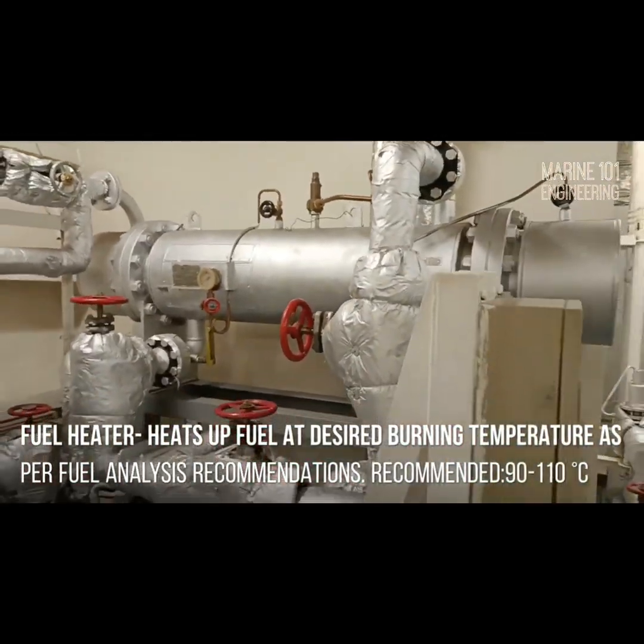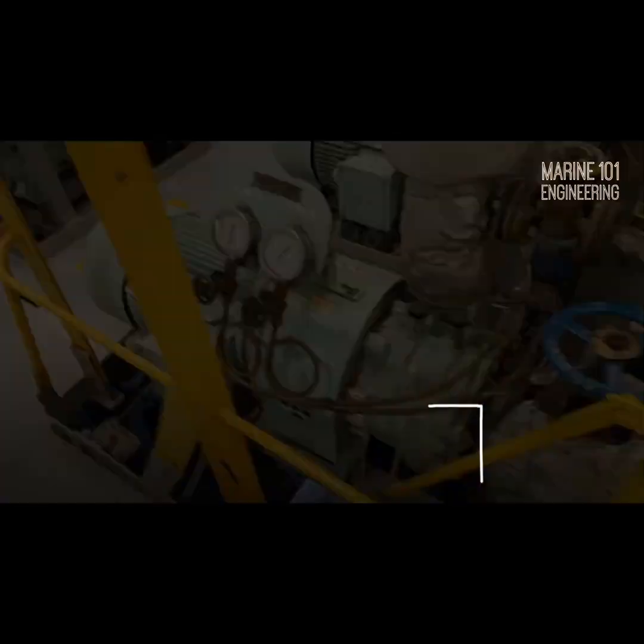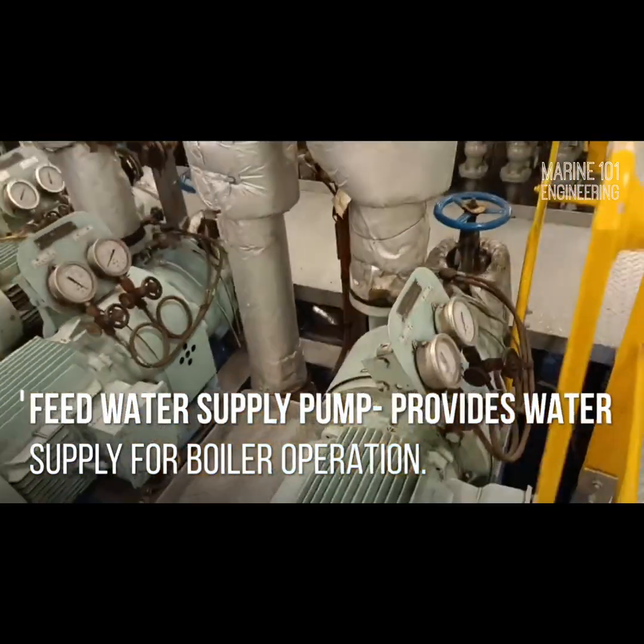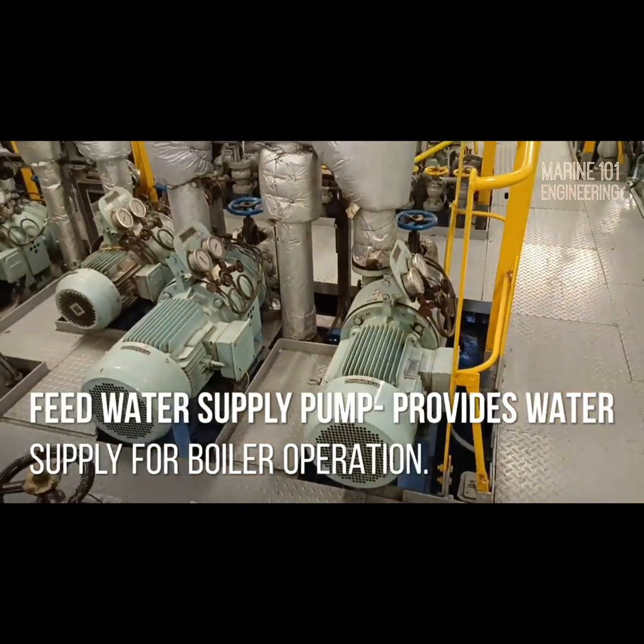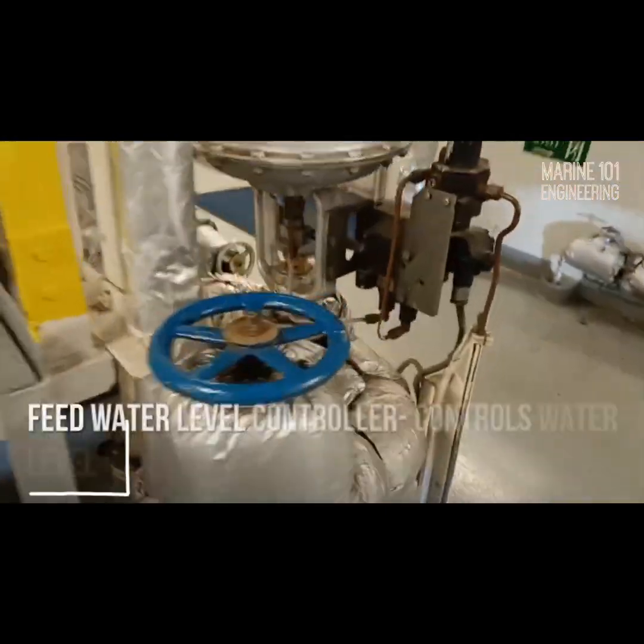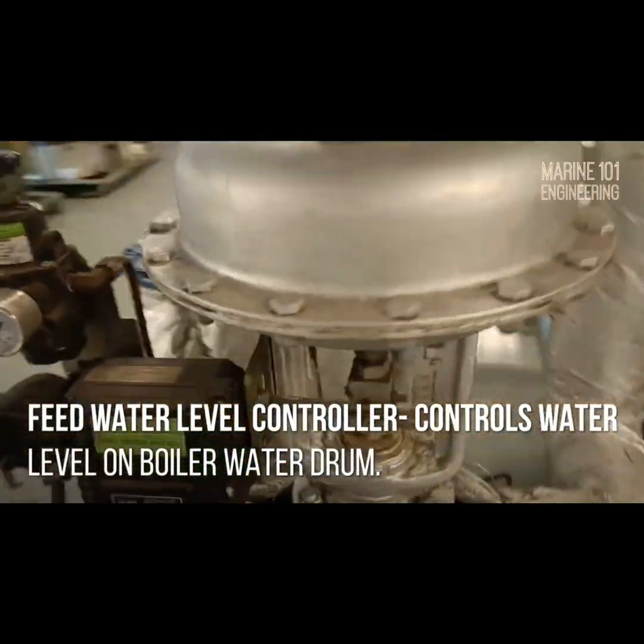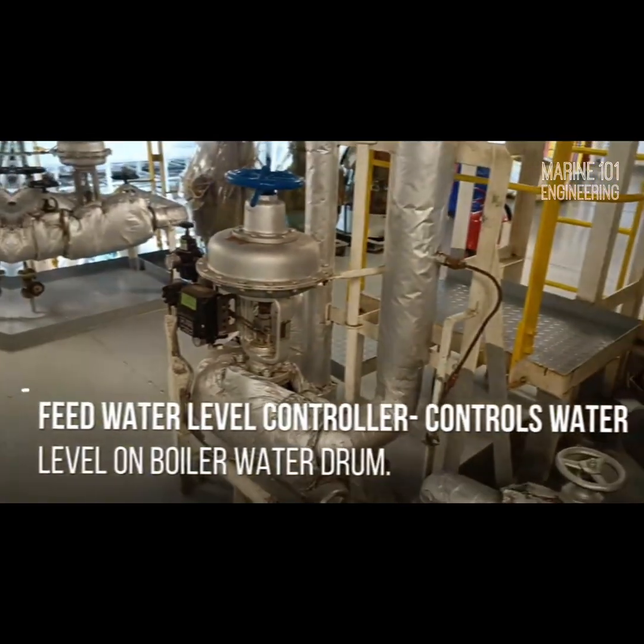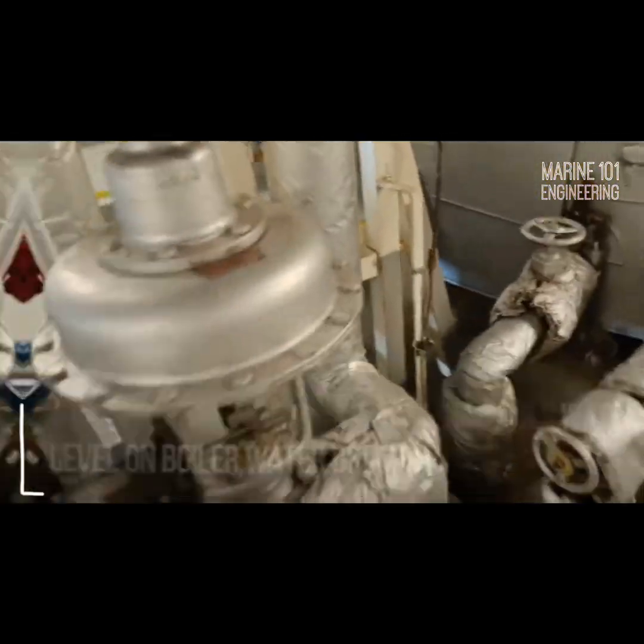Fuel heaters regulate fuel temperature for combustion. Refer to laboratory analysis for correct setting. Applicable on HFO use only. Feed water supply pumps deliver water into the boiler tube for steam production. Feed water level controller automatically regulates water level during firing and even on standstill.